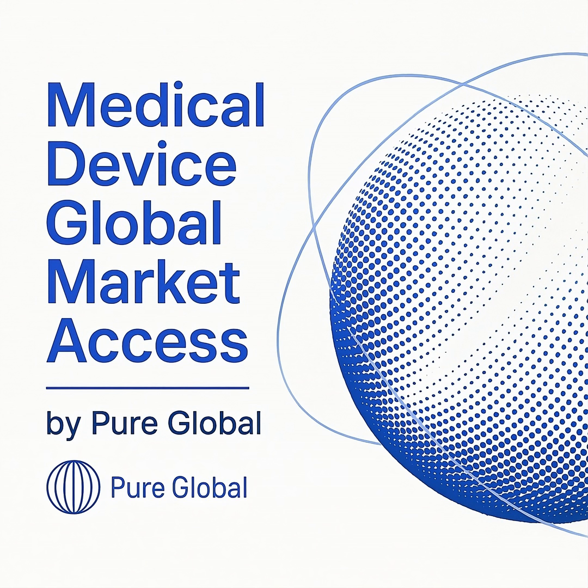Despite this extension, there are mandatory actions. All medical devices, regardless of whether they bear a CE or UKCA mark, must be registered with the MHRA before being placed on the Great Britain market. If the manufacturer is based outside of the UK, they must appoint a UK responsible person, or UKRP. This entity must be based in the UK and acts as the legal representative, handling tasks like the MHRA registration on the manufacturer's behalf.